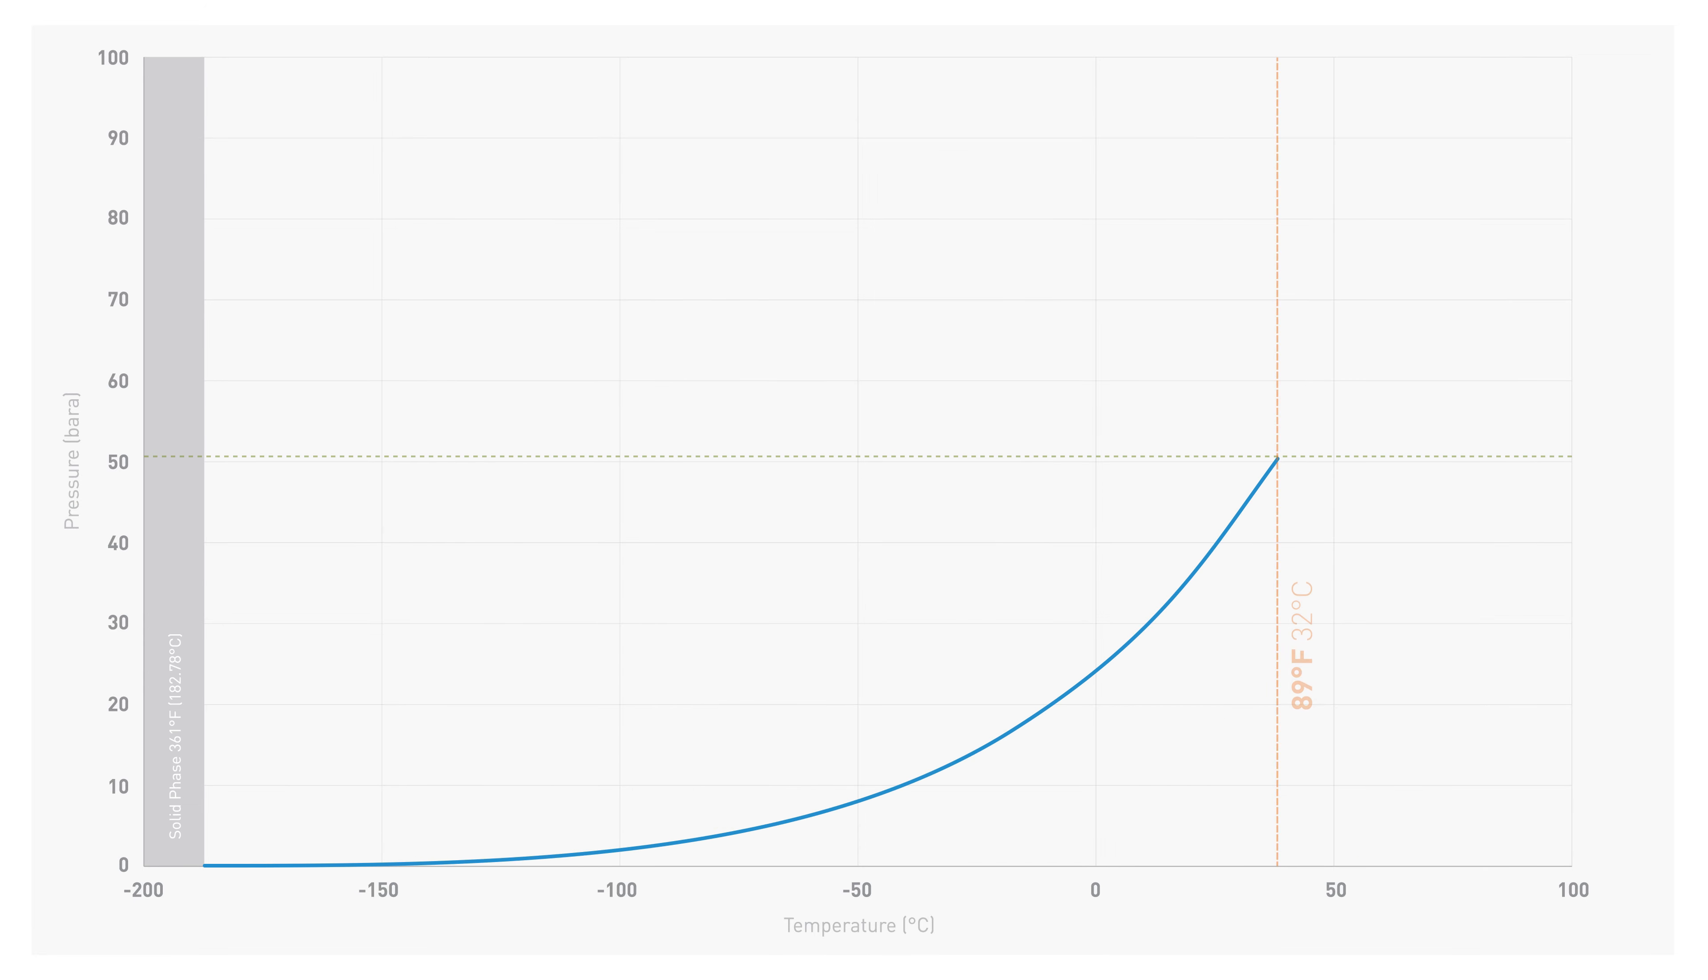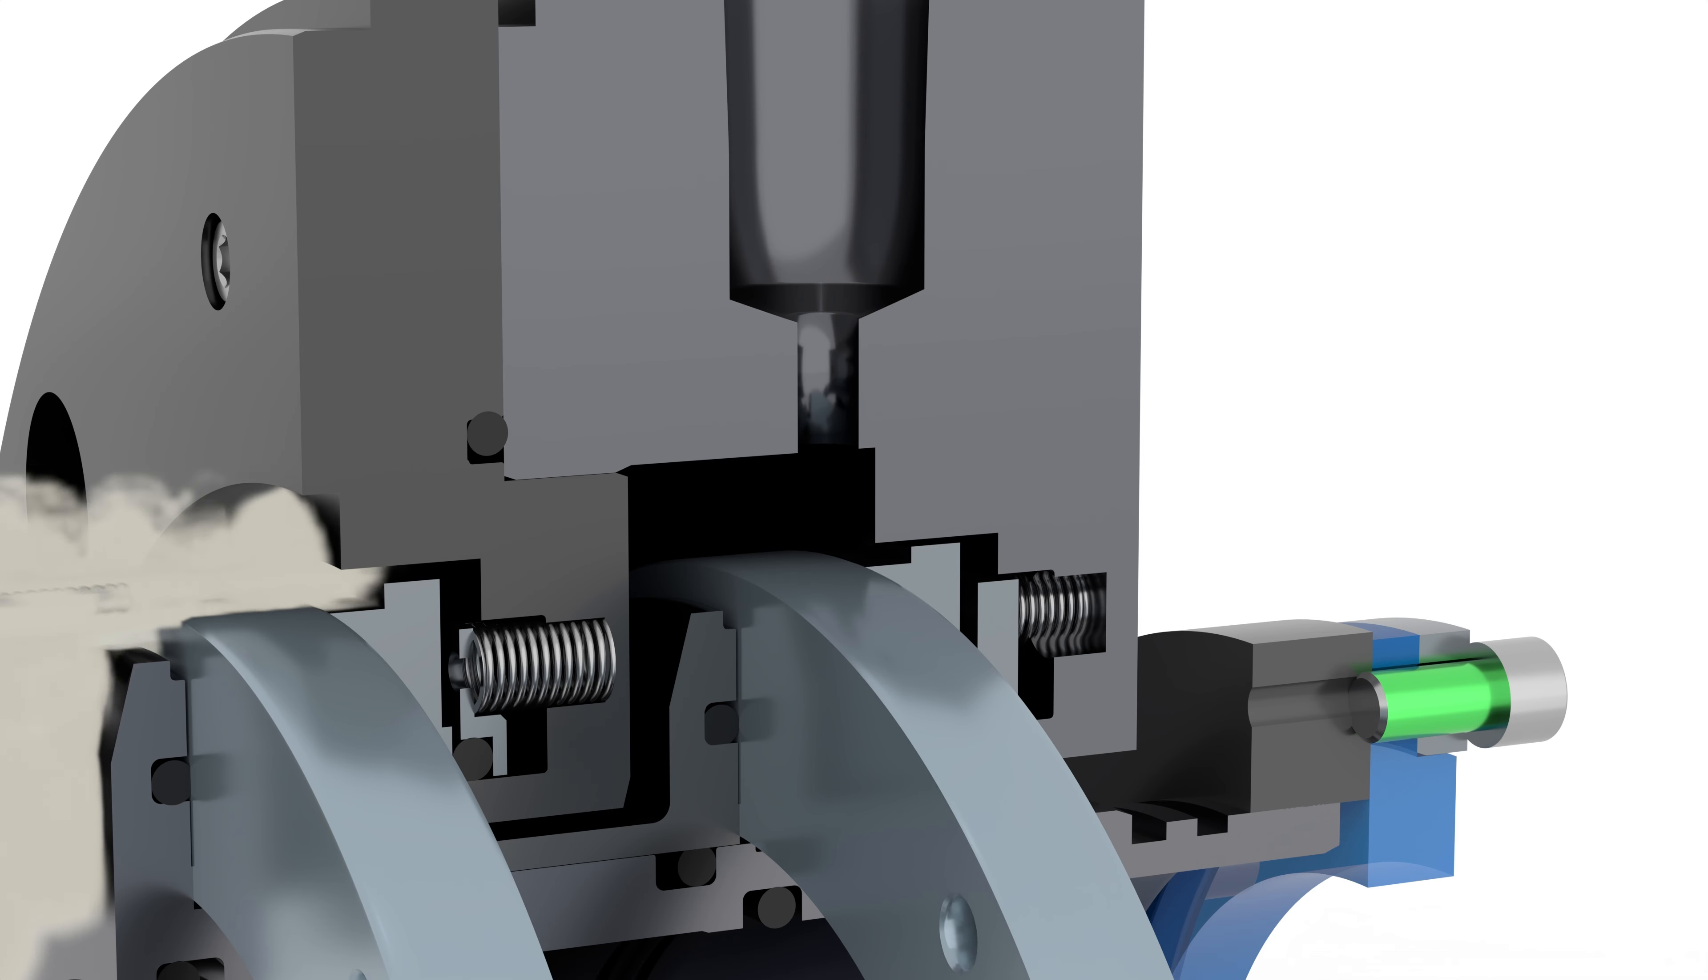When critical temperature is eclipsed above 89°F (32°C) and pressure exceeds the critical point of approximately 760 psi (50 bar), the phase diagram indicates that ethane will exist in a supercritical condition or a dense phase, sometimes referred to as a pumpable vapor.